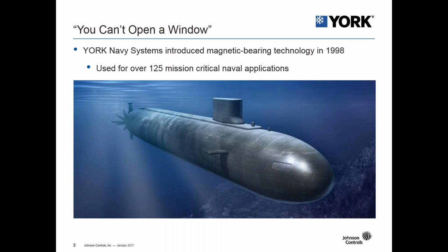So as an intro into the different bearing options, just wanted to show a Navy submarine. York successfully introduced magnetic bearing technology in 1998 in the York Navy systems, and it's been used in over 125 critical Navy applications throughout the world. So it's very important that the right technology is chosen for these type of applications, because if you don't have a chiller and it's down and it's not operating, you can't open a window to reject that heat.